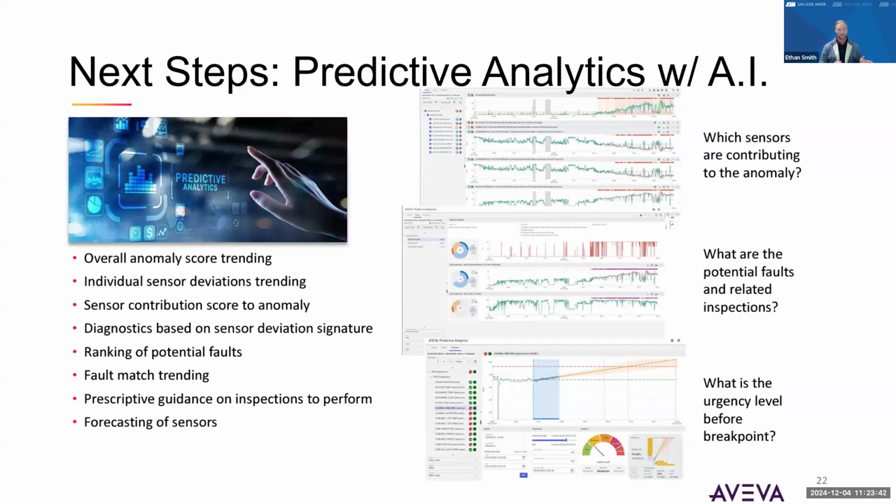These are the parameters that are going a little bit off. Our system says this is likely a bearing failure or wires overheating, et cetera. And it can actually give us an estimated timeline of when that failure might happen. And so we can really drive our downtime and our failures as close to zero as we can, and just have a really robust asset management strategy going forward.